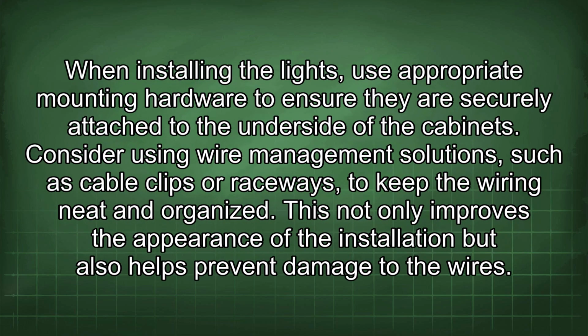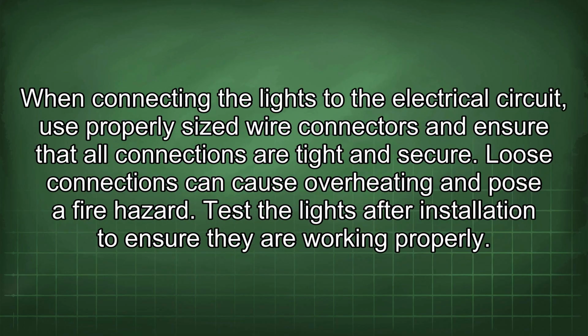When installing the lights, use appropriate mounting hardware to ensure they are securely attached to the underside of the cabinets. Consider using wire management solutions such as cable clips or raceways to keep the wiring neat and organized. This not only improves the appearance of the installation but also helps prevent damage to the wires. When connecting the lights to the electrical circuit, use properly sized wire connectors and ensure that all connections are tight and secure. Loose connections can cause overheating and pose a fire hazard.